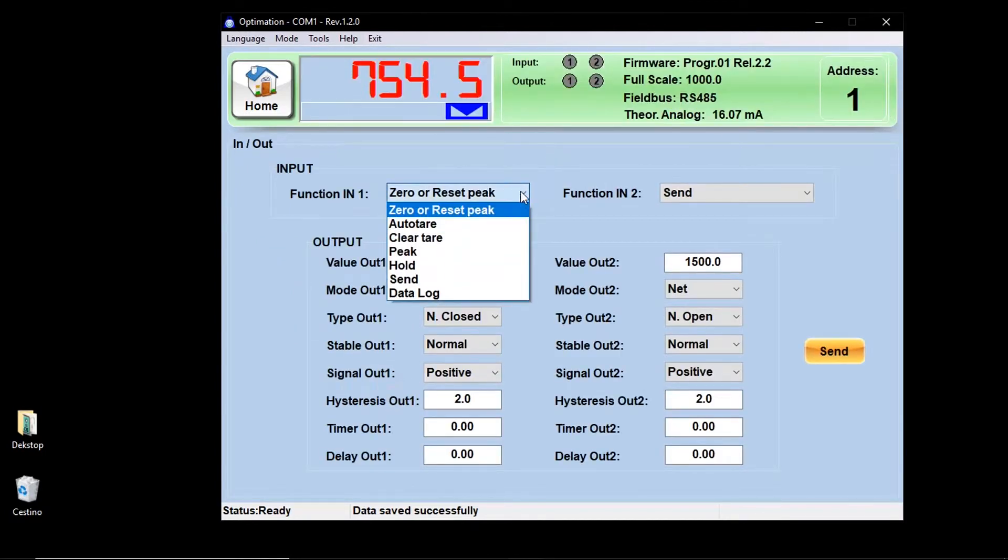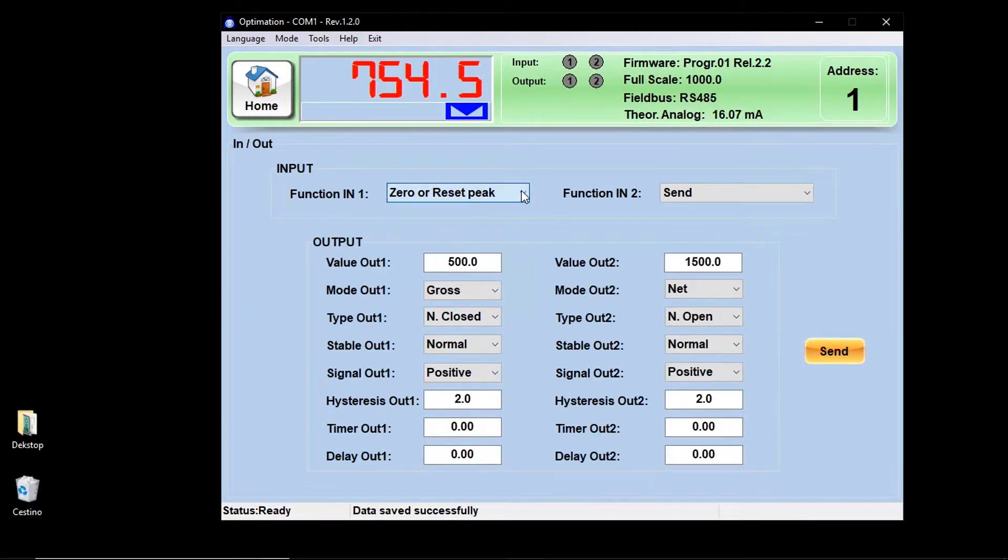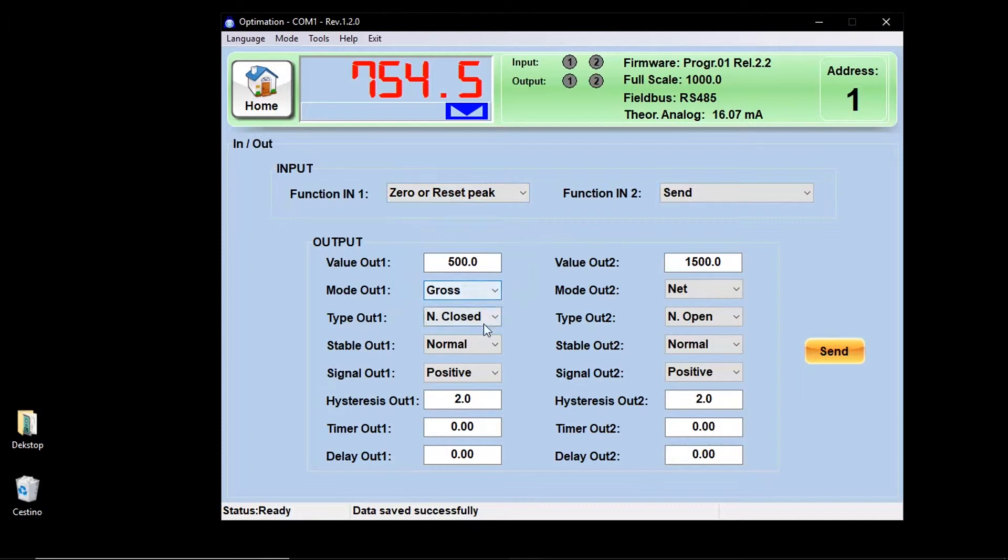With the in and out function key, you can access the input and the output menu and you can select which function to combine with the inputs, set the output thresholds, and all the related parameters such as mode, type, stability, signal, hysteresis, time, and delay.